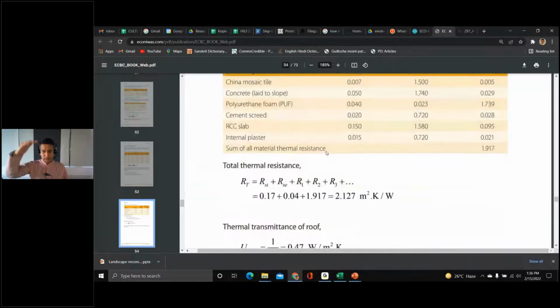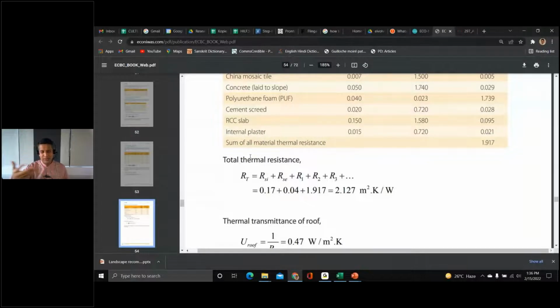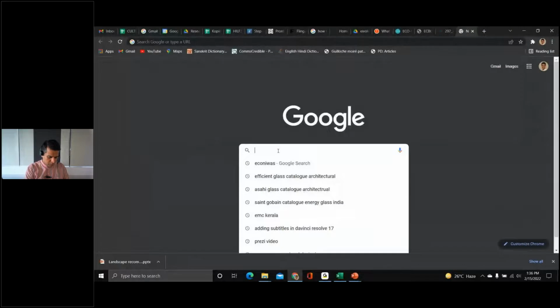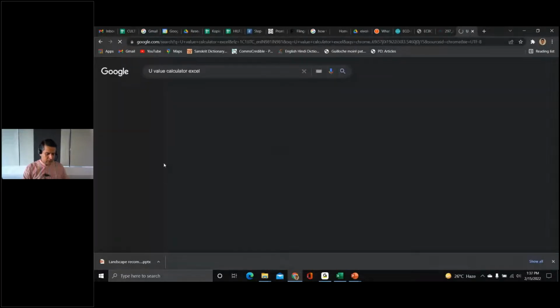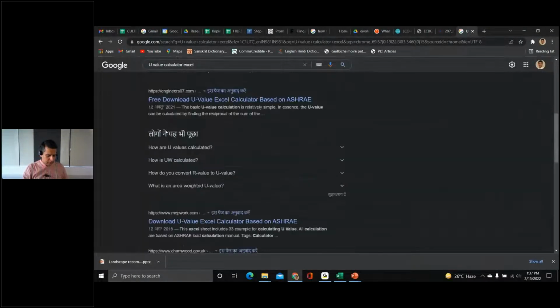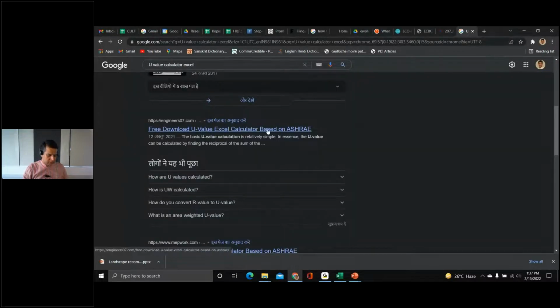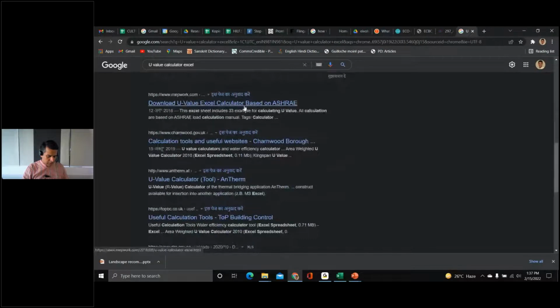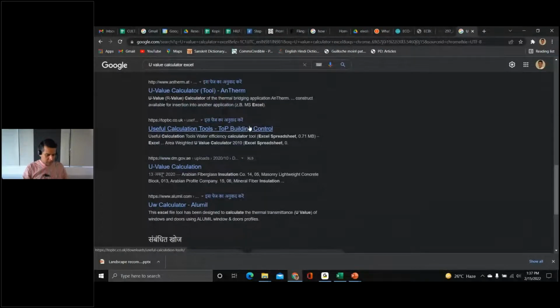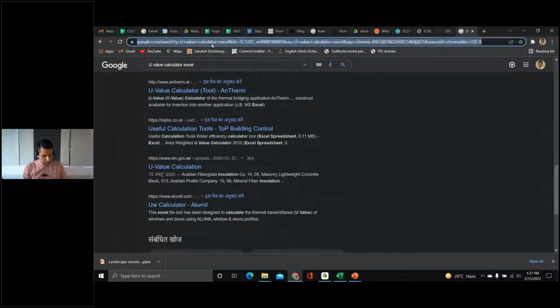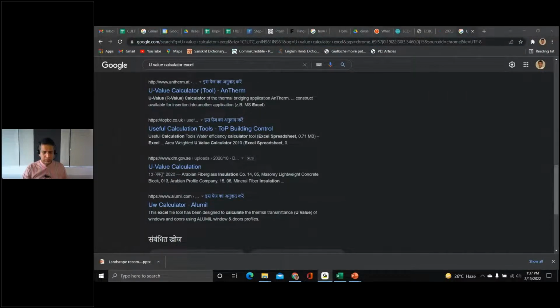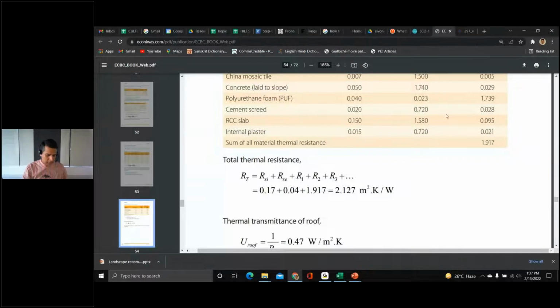So the total thermal resistance - this is one way of calculating it, but normally you don't need to go into this kind of calculation. There are software or even Excel sheets available on the internet. If you just go to Google and search U value calculator Excel and press enter, you'll get lots of U value calculators - free download ones based on ASHRAE, and others. I'll copy paste this link for you guys in the chat box so you don't have to calculate this physically yourself. You should know the principle behind it, but that's about it.